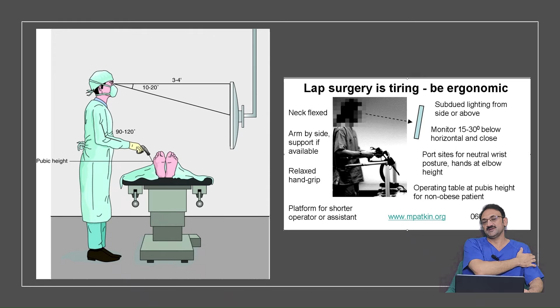Yes, the lighting is really very important. It is mentioned here. While looking at the monitor, the lights of the operating room in front of you and on both sides should be turned off, so that you should not get a glare, number one. Number two, your macula should not get strained, because if I'm looking at the screen right in front of me and there is a light in front of me on the roof, that light is impacting my retina and my macula, so I will not be getting the full colors, and the depth perception and the tissue perception will be impaired. So all those lights should be turned off. Okay, so moving on to the next slide.